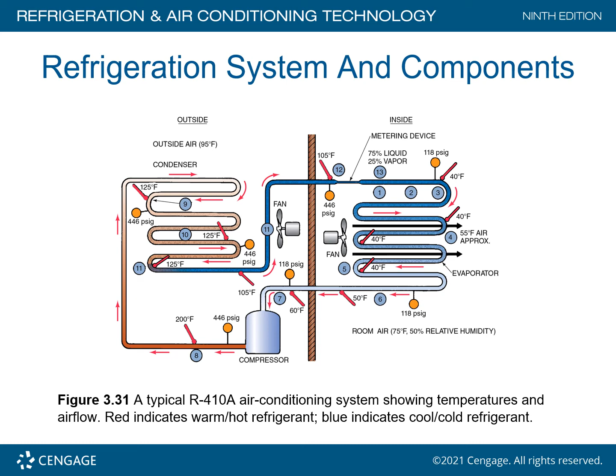We now enter the condenser coil. We're now at 125, and over here at number 9, notice what happens to the refrigerant vapor. It is cooled because we're surrounding that high temperature, high pressure gas with cooler air. As we're doing this, that refrigerant vapor gradually turns into liquid, and once we come back down towards the end of the condenser, now we have liquid refrigerant. The red indicates the warm, hot refrigerant, blue indicates the cold refrigerant. Remember, we have vapor all the way up to the condenser. And once the condenser goes through its process of removing heat from the refrigerant, this cycle repeats itself.